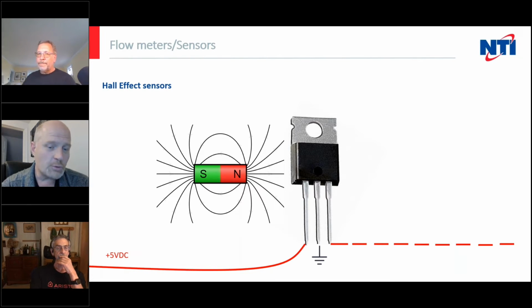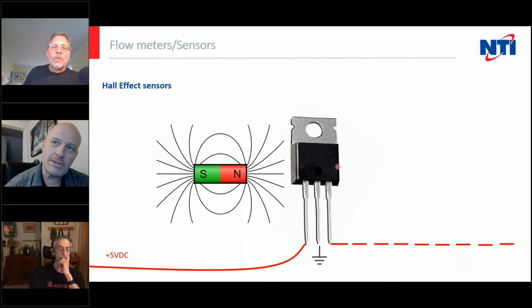The controller can count those pulses, and basically based on the number of pulses, it knows how fast something is moving, or how much water you're using, or if it's a car, for example, how fast you're going. So fairly simple devices, unfortunately not the easiest things to test when we're in the field, because our voltmeters just aren't set up to read that pulsed signal coming out of them. But they should have some sort of low voltage going into them. Typically there's a ground pin, and don't take this picture as a hard and fast rule for what it's going to look like. Typically they don't look like anything because the sensing element is embedded somewhere. So we're going to show you a real example here in a second.